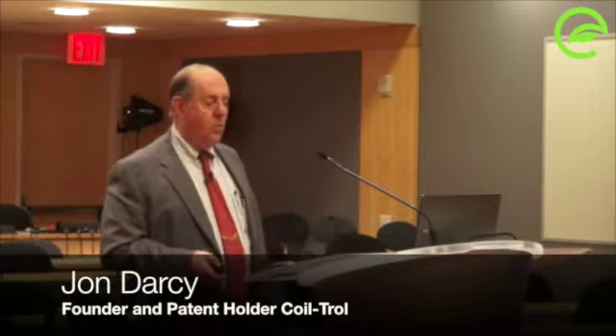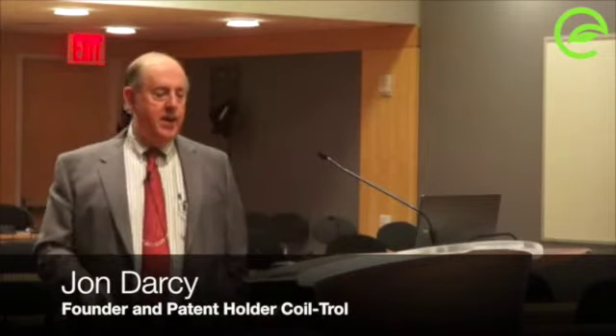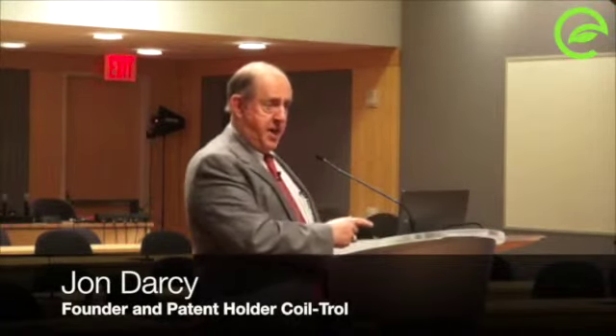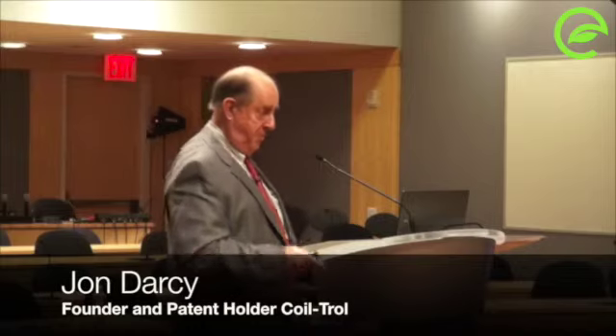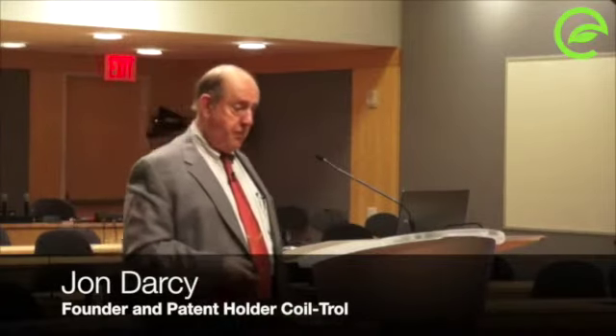What were the criteria for starting air conditioning last week, when it was 60, 63, 64, but it was dry, and the sun load was pretty heavy? Most of the people started a chiller last week based on the sun load in the tower of the building. The rest of the building could be satisfied with 62, 63, 64 degree air, pulling that 100% outside air through the economizer cycle, and then they picked up 1 or 2 degrees across the fan, and for the most part, places were satisfied.